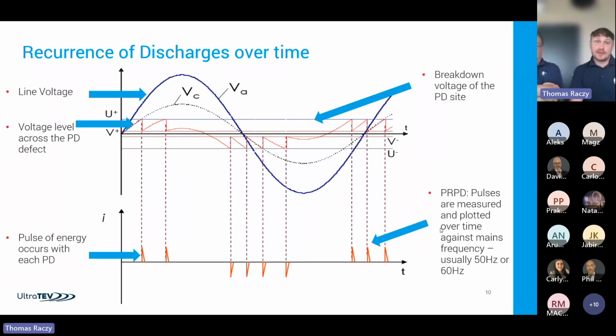Okay, so before we actually discuss various types of discharges and various sources of discharges and related phase resolved patterns, it would be really good to quickly overview how the actual partial discharge pattern is created. So what we're looking at here is a graph that you probably might have seen before in various literature. We're looking at the line voltage, so VA. That's the voltage across the healthy part of the insulation as per design, designed to take that voltage without breaking down. And we're also looking at the VC, so that's the voltage across the cavity.